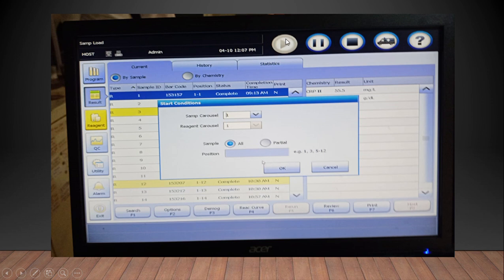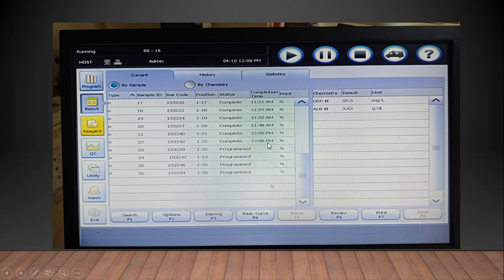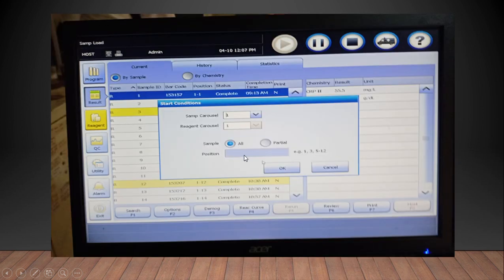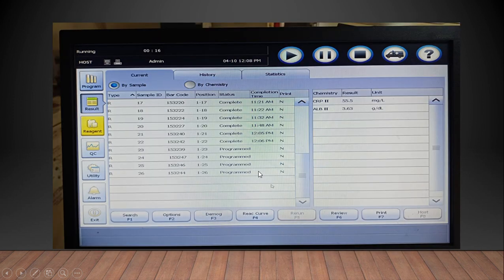So that is the start. This is sample carousel 1, and you don't have to worry about the reagent carousel here. So it is at 1. Now if you select all and give OK, the instrument is going to check all 40 positions for samples. But we have given samples only from 23 to 26. So you select the partial button and give the numbers 23 to 26. Select partial, give 23 to 26, and then give OK.